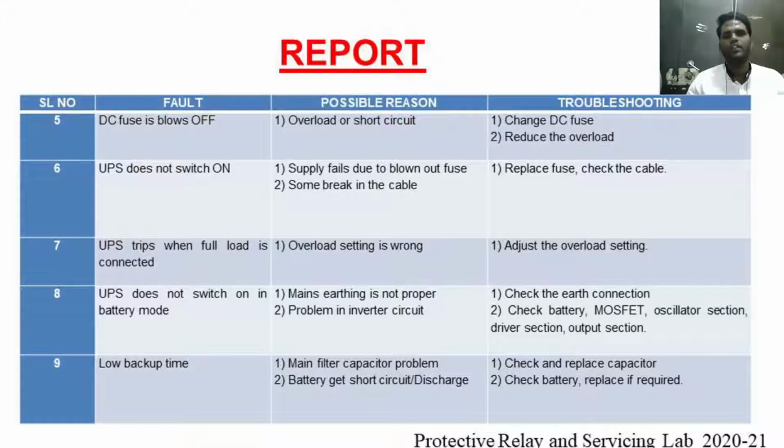So next one is that the UPS trips when full load is connected. This happens because the overload setting is wrong. For this one, I need to adjust the overload setting in a proper manner so that it can withstand the overload conditions.